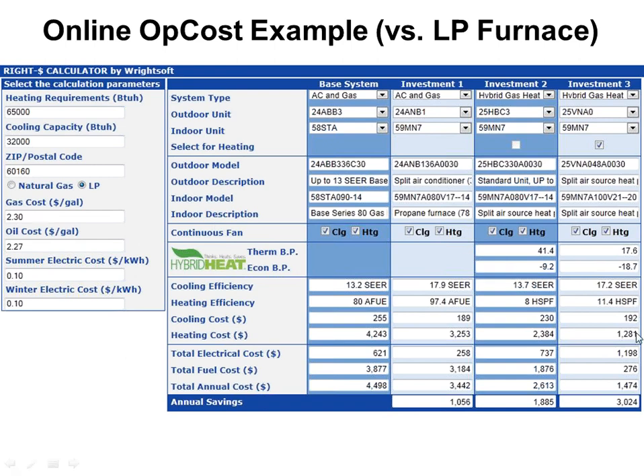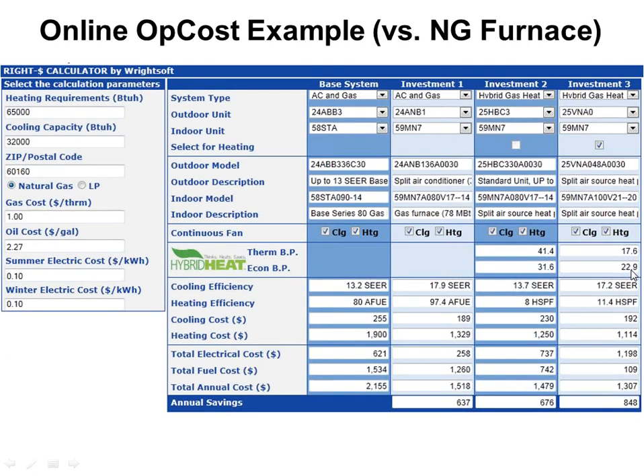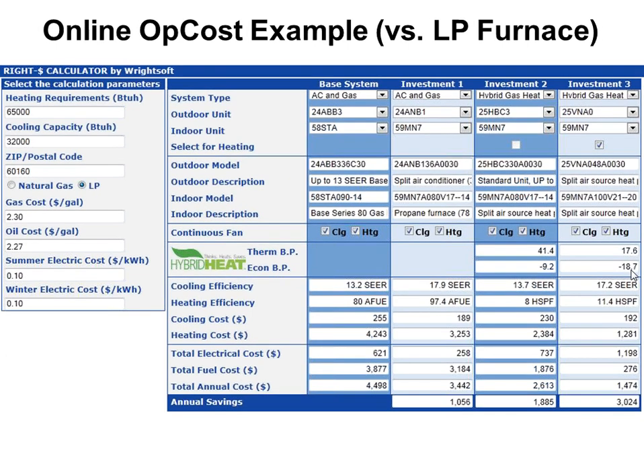And this guy, the thermal and economic breakpoints are, well, the thermal breakpoints are the same because they're the same furnace and heat pump. The economic breakpoint's different. So thermally, I can get down to 17 degrees just like the gas system. Economically, it's minus 18, whereas the gas one you saw was 23 degrees. Well, now it's saying run your heat pump down to minus 18, then put on your propane furnace. Now in the real world, I can't do that. I've got to switch at positive 18 because I need to be able to get the thermal capacity and the economic benefit. But it's basically showing you here that propane is so overpriced compared to electricity that it always makes sense to run the heat pump.